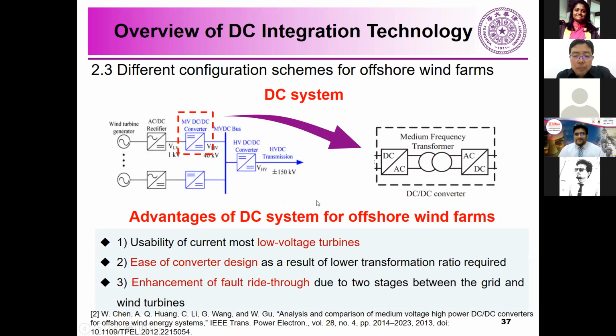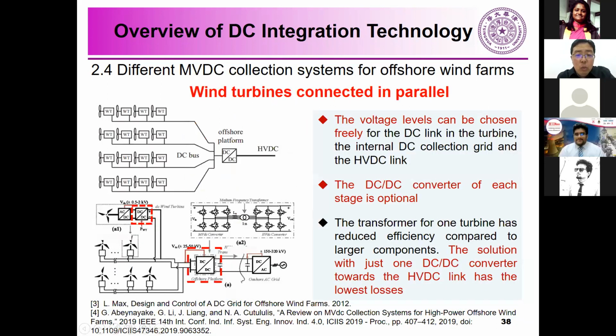Okay, and we also have some detailed integration technologies for the wind turbine connections. For each wind turbine the power is small, so we need to connect multiple wind turbines. The wind turbines can be connected in parallel. With this solution, the voltage levels can be chosen freely for the DC link in the turbines, the internal DC connections, the collection grid and the HVDC link. The DC-DC converter of each stage is optional. Also the transformer for one wind turbine has reduced efficiency compared to large components. So the solution with just one DC-DC converter towards the HVDC link has the lowest losses.